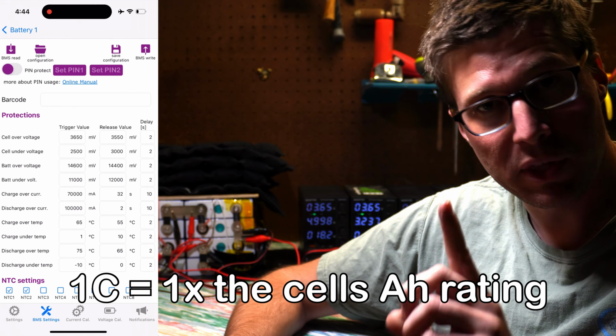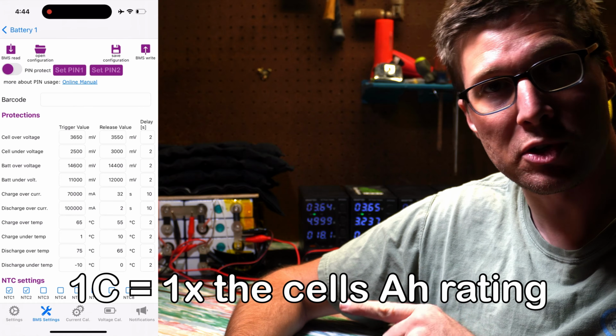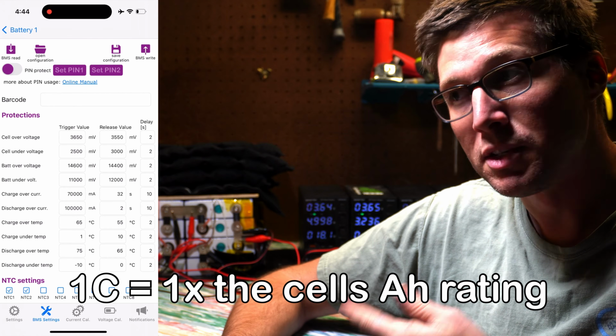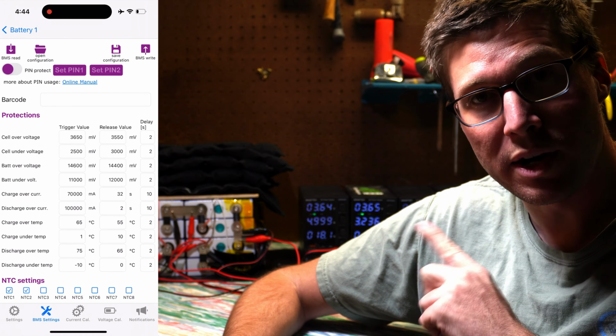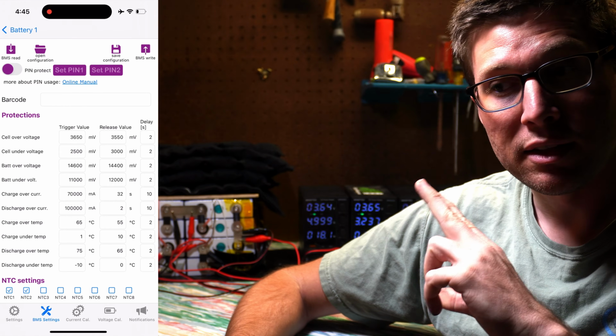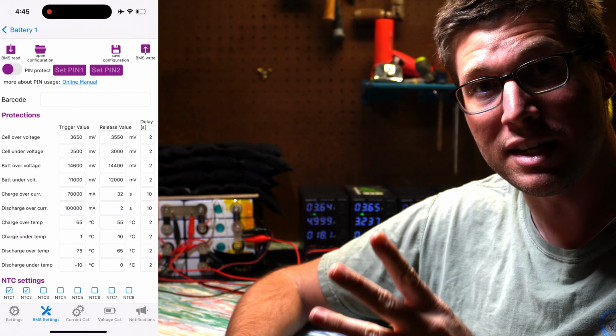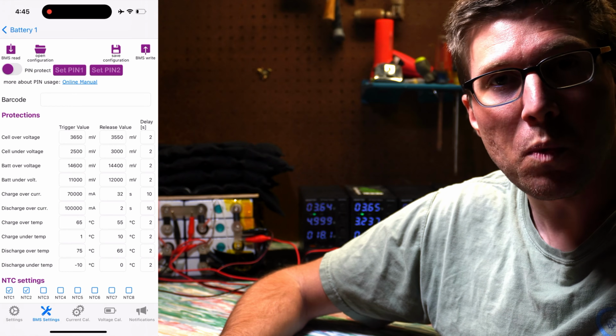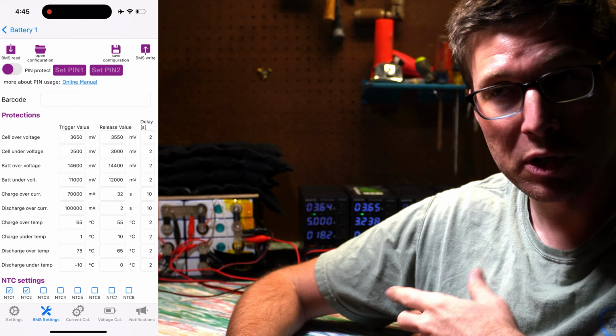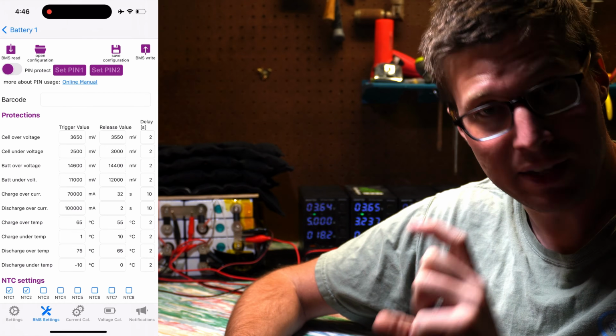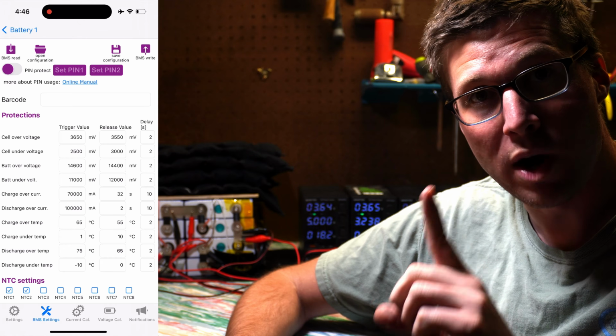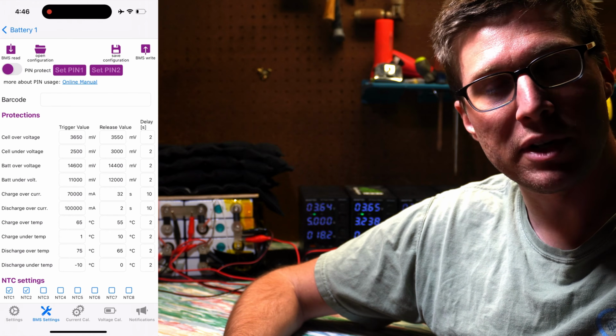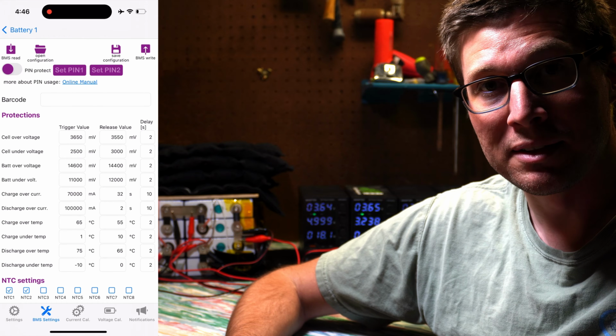So 1C, with a capital C, means the battery can charge or discharge at 1 times its rating in amp hours. Since these are 100 amp hour batteries, 1C is 100 amps. 2C would be 200 amps. 3C is 300 amps. Now these batteries are rated to momentarily, for about 3 seconds or so, do 3C, but it's going to damage the battery in the process. So why do that? If you need 3C, get more batteries. To keep things happy, we're going to be charging at no more than 0.7C and discharging at no more than 1C. That's a nice safe number. It keeps everything happy. The batteries can do much more than that, but why push them?